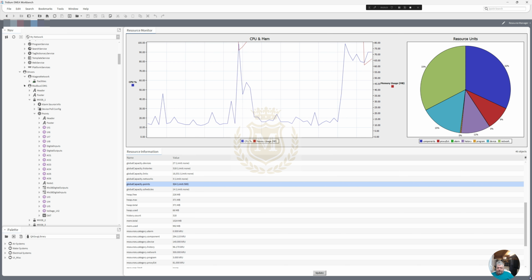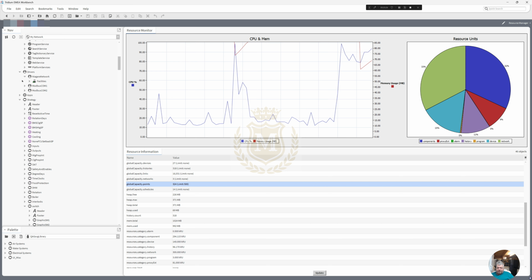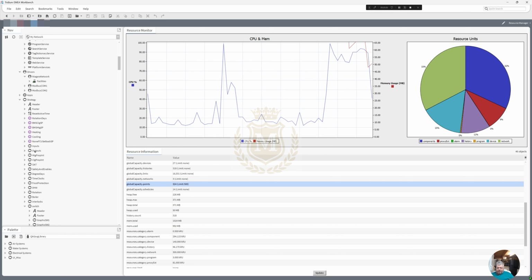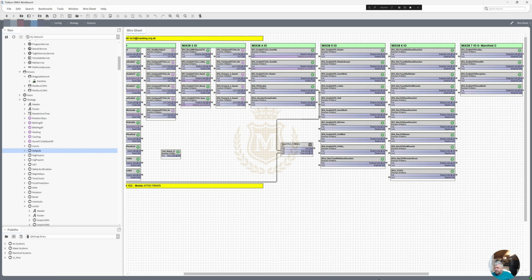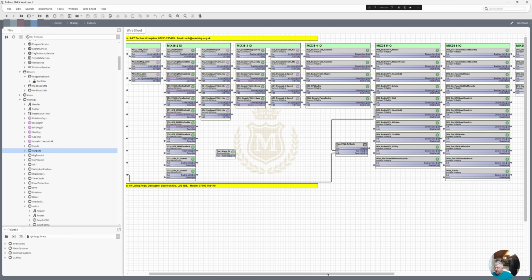Right, where was we? We've done Modbus. We were looking at the strategy, weren't we? So there was our inputs. These are our outputs. So these 1, 2, 3 and 4 mixes are actually in the panel. These 5, 6, 7 are manifolds. They're not in the panel, but they're networked via Modbus RTU 2-wire, not IP. I explained why some of these were overridden, and everything else seems to look okay.